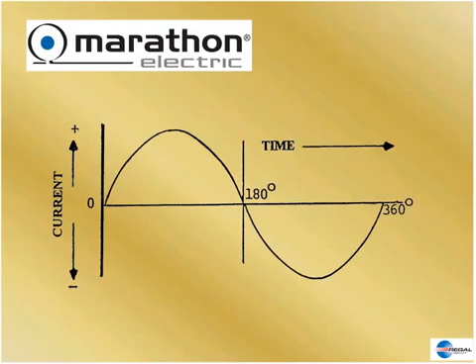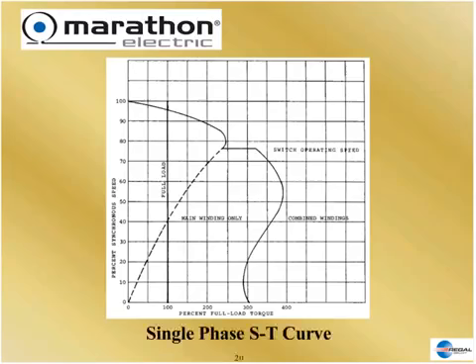Now, back to single phase. It rises and falls; it can't travel. How are we going to make this wave go around our stator with only one phase? We artificially get it to move off these dead-center points by using an auxiliary winding, usually called a start winding. The analogy is the starter in your car — you turn the key further, engage a starter motor, it kicks the engine over. Once the engine fires, it can run but it can't start by itself. It's the same with single-phase motors: they will run, but they won't start.